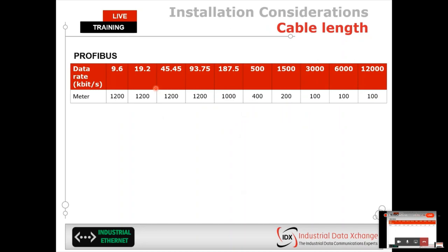Last week we spoke about the different network speeds you can run in PROFIBUS. You can choose that network speed, anything from 9.6 kilobits per second up to 12 megabits per second. Depending on how fast you run the network, that determines how long the cable can be in a specific segment. For example, our favorite baud rate, 1.5 megabits per second, my total segment length can be a maximum of 200 meters. If I go any faster, it's a maximum of 100 meters.